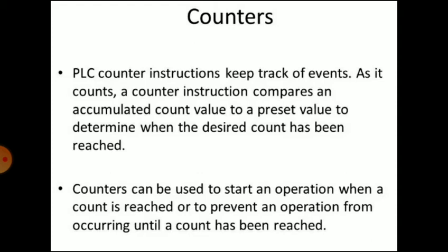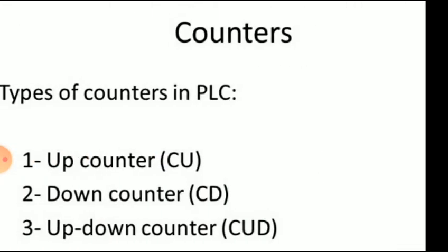As it counts, a counter instruction compares an accumulated count value to a preset value to determine when the desired count has been reached. So counters can be used to start an operation when a count is reached or to prevent an operation from occurring until a count has been reached.